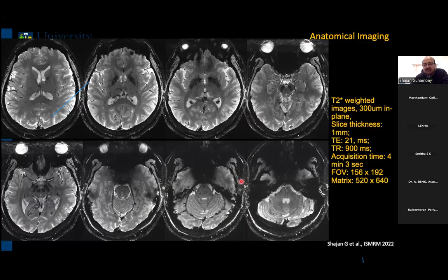So to summarize my second topic, MRI at ultra high field is challenging due to shorter wavelength in tissue, and you really need parallel transmit arrays to mitigate this transmit field inhomogeneity that is caused by the shorter wavelength in tissue. And you need these dual row transmit array coils to extend the longitudinal coverage. And if you combine transmit arrays with these high density receiver arrays, you can improve the SNR. And as always, when you increase the channel count of the receiver arrays, it improves the parallel imaging performance.